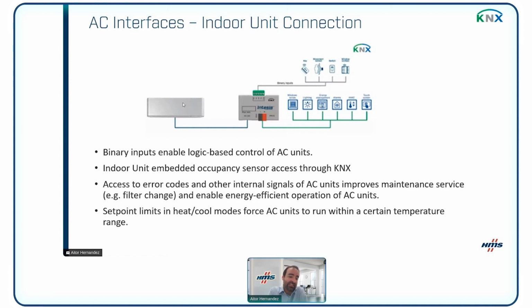Related to maintenance, we can access all error codes, okay? There are a lot of error codes in those kinds of machines, and we can act according to the error code. For example, we can get an overheating error code, and we can decide to stop or to perform a set point action in the unit in order to reduce or stop this error code, okay? And of course, we have the set point limits. It is very normal that people in the room try to raise the set point to a high limit. Okay, for example, it makes no sense to set 32 degrees Celsius in a room, so we can control and read those limits in order to block this functionality for the final user in the room.